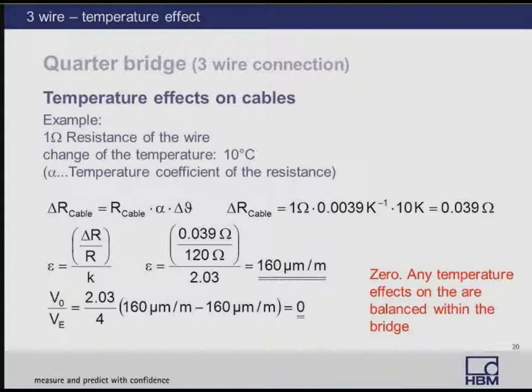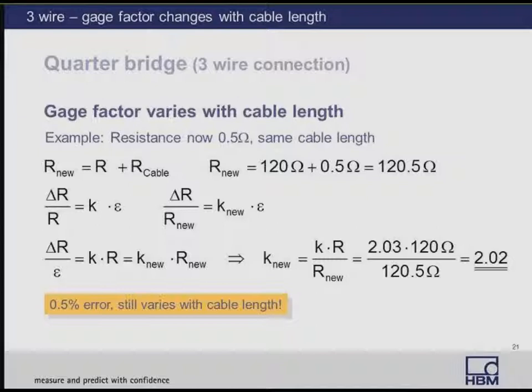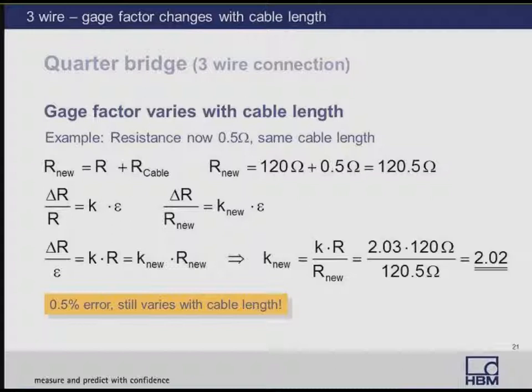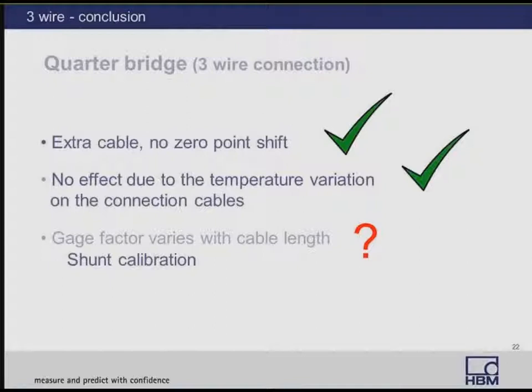The last issue with a three-wire configuration is the effect on the gauge factor. The additional cable length does cause a change in gauge factor result. This signal loss occurs due to cable resistance and can be considered a reduction in the effective gauge factor. The lead resistance adds 0.5 ohms to the strain gauge, and solving for K, the gauge factor changes from 2.03 to 2.02 — a 0.5% additional error caused by the leads. In conclusion, a three-wire connection eliminates zero-point shift and lead wire temperature variation concerns, but the gauge factor still varies with cable length and needs to be considered.